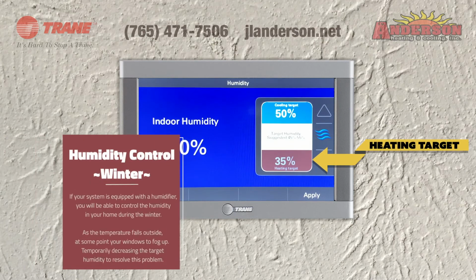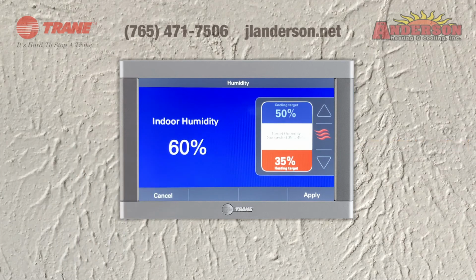With this system, we have a humidifier. So what a humidifier does is it runs in the winter, and that's why it's red. I'm going to hit that button now. The thermostat controls the humidifier based on the indoor humidity. Right now we have the humidity set at 35%, which is pretty average for a house in this area. When the humidity in the house falls as it gets colder and colder outside, at some point in time the humidity is going to drop below 35%. And when that happens, every time the furnace is running, it is going to bring on the humidifier.